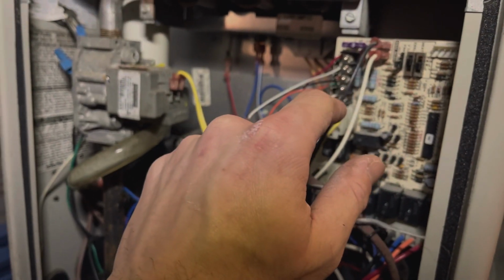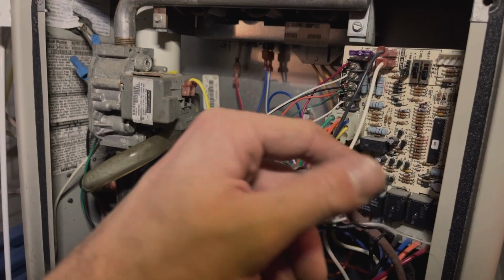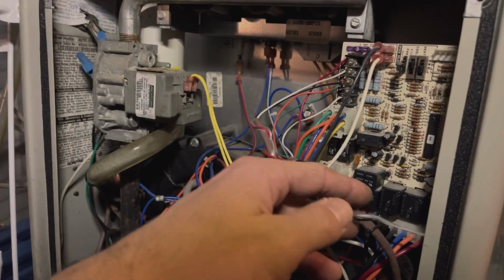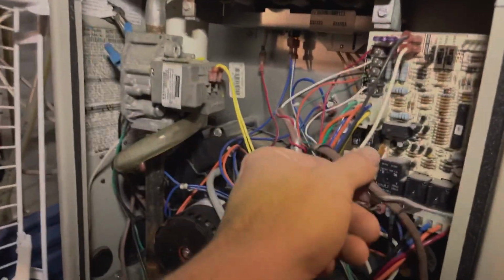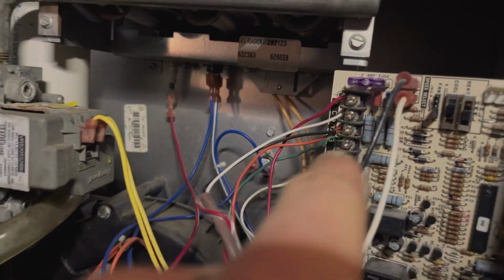But anyways, you normally will just have one thermostat wire coming to the furnace, and if you believe that could be your issue, if you don't hear it kicking on the furnace, then it's probably not calling for heat, and you might have an issue with your thermostat wire. So you can check to make sure that these are connected and tightened properly.